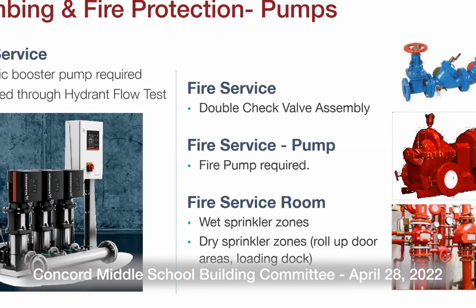So I was saying for the water service, after the flow test, a water booster pump is required. It's going to be a small one, 3 horsepower each pump. It will be duplex with variable speed each pump.